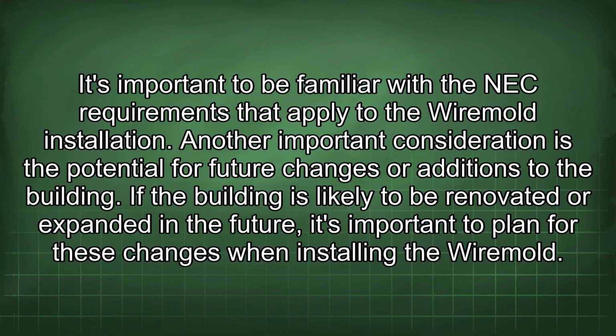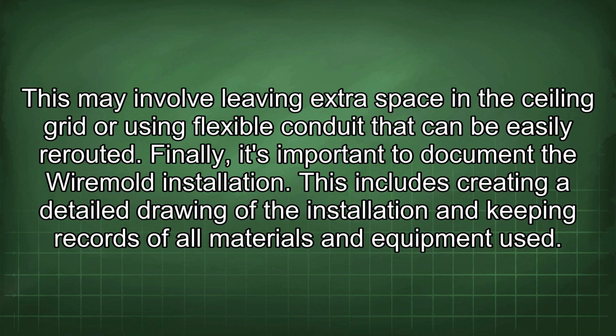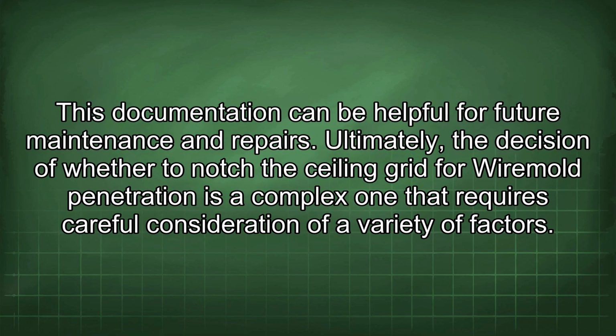Another important consideration is the potential for future changes or additions to the building. If the building is likely to be renovated or expanded in the future, it's important to plan for these changes when installing the Wiremold. This may involve leaving extra space in the ceiling grid or using flexible conduit that can be easily rerouted. Finally, it's important to document the Wiremold installation. This includes creating a detailed drawing of the installation and keeping records of all materials and equipment used. This documentation can be helpful for future maintenance and repairs.